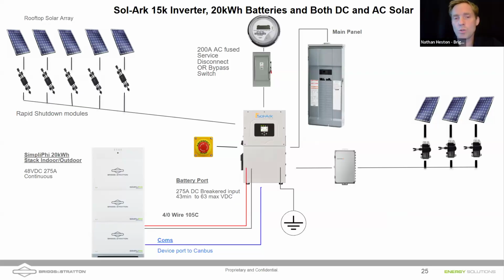They also brought in a new solar array to bring more power in, and they DC coupled it, which is more efficient, right? So if you're DC coupling solar, you're taking the DC output of a solar array, feeding it through an MPPT, and going to the DC input of a battery. Instead of each time you convert between AC and DC, you lose some percentage. And so keep that in mind. You know, if you're doing an AC coupled array, you're already going to lose some percentage in terms of round trip efficiency when you're charging your batteries up. A DC array is more efficient. So you can absolutely do both.